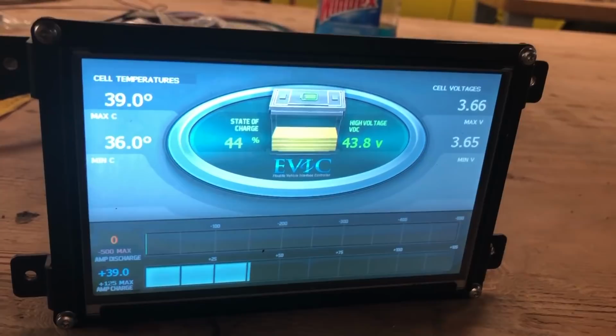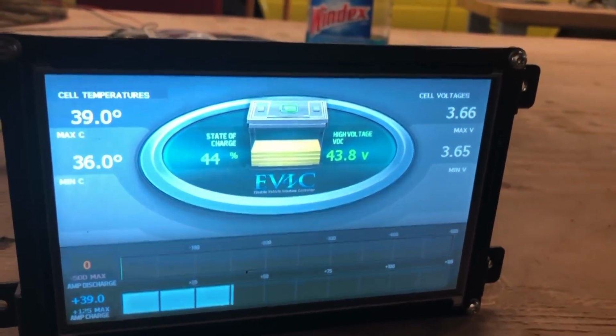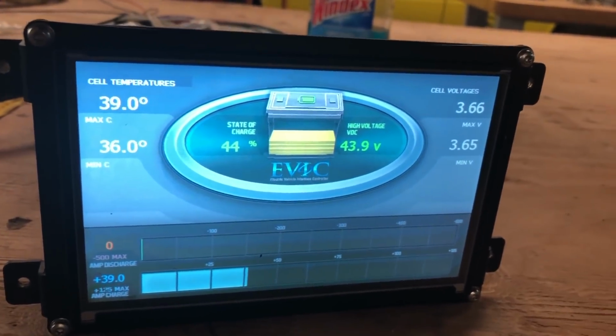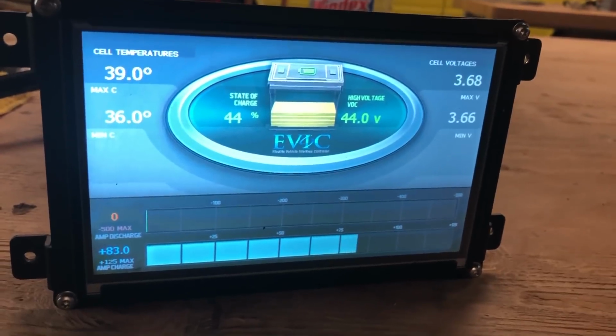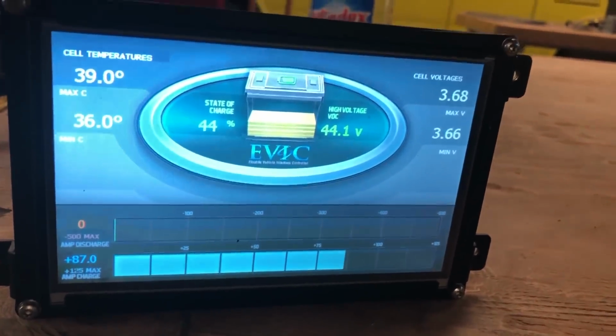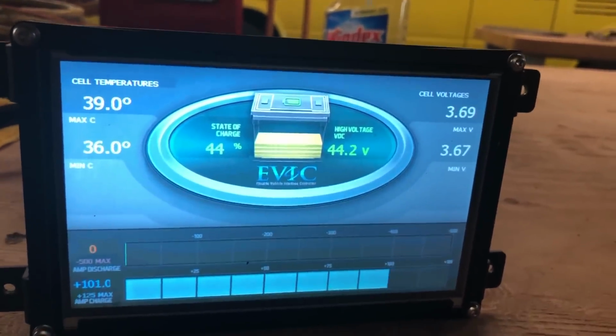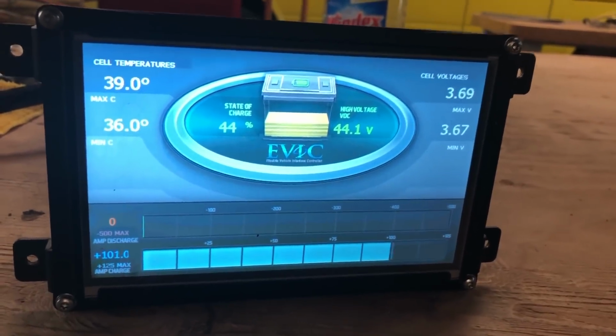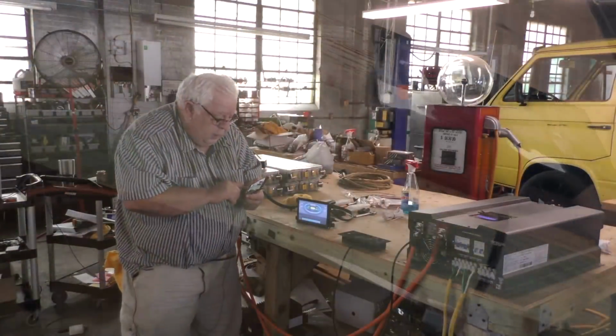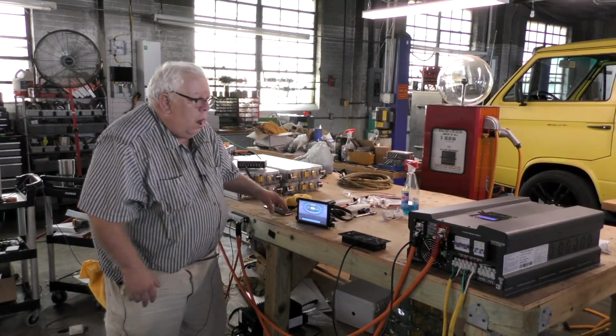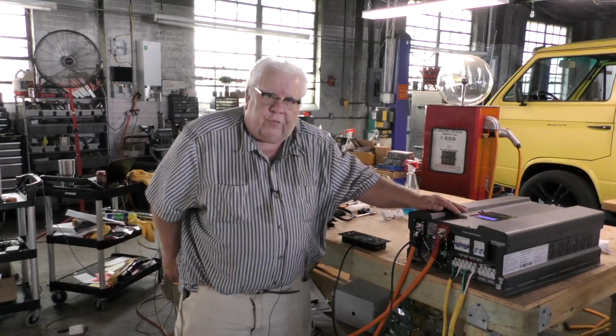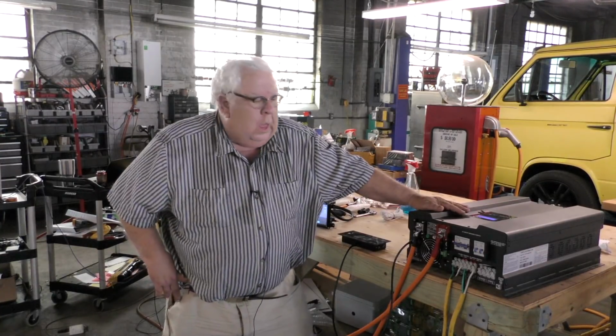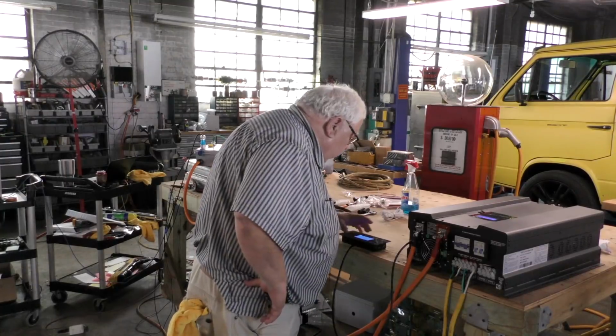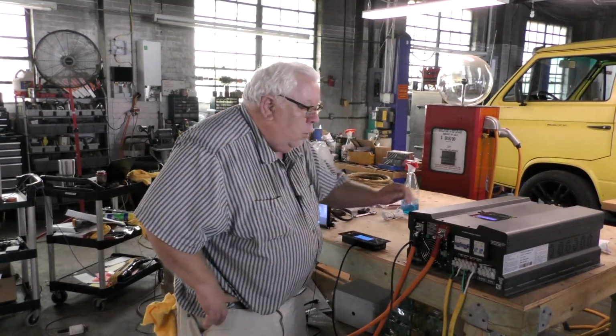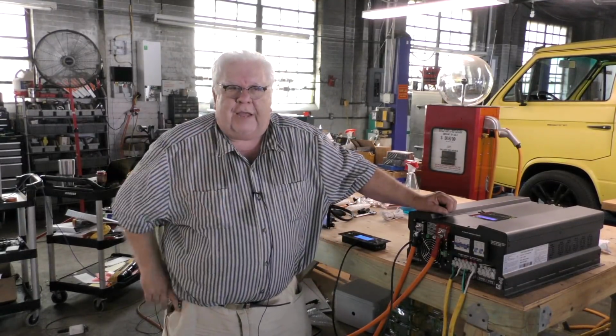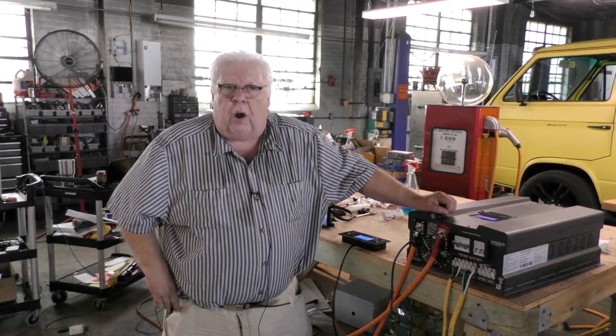That's about 5 minutes there. It's about 5 minutes and 10 or 15 seconds to bring it up. So let's see if we can catch it here. And there it goes. And number 4 has come up. We're now shooting 87 amps into the device, into the batteries. 101 amps. And I can hear our fans coming up, but note this thing has been strangely silent. It just doesn't whimper at all, but at this point we're doing at 100 amps about a 35% load. It thinks it's making about 4,000 watts of power.